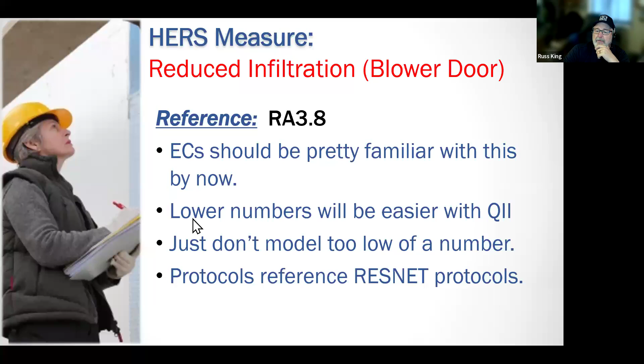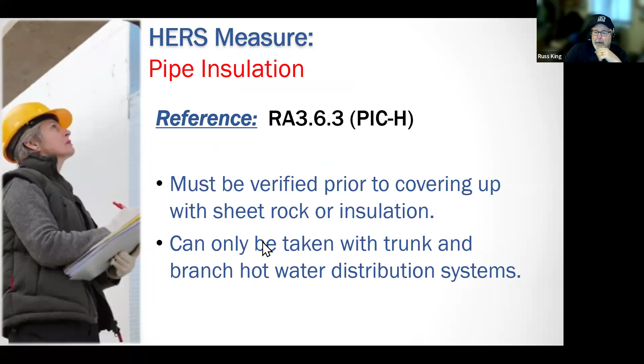All right. The house is leakier than it's supposed to be. Most of that leakage is behind the sheetrock. But there may be things like there's no backdraft dampers or something like that causing it to fail that they could fix pretty easily. It should be easier to pass with QII because QII ensures a continuous air barrier. Must be verified prior.